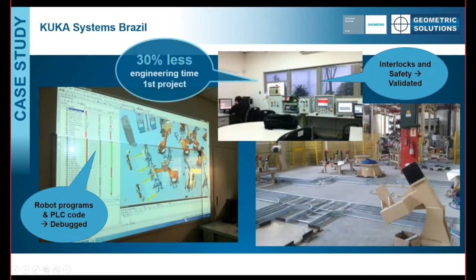With virtual commissioning, I'd take the simulation, look at these sensors, and that would be my input into the PLC. When the sensor got triggered, the PLC would understand that, and then the PLC would give instructions to the simulation to operate, so machines would move, clamps would clamp, motors would turn, then more sensors would trigger, feed it back to the PLC, and it would give the next set of commands to the tools. We tested all that up front.